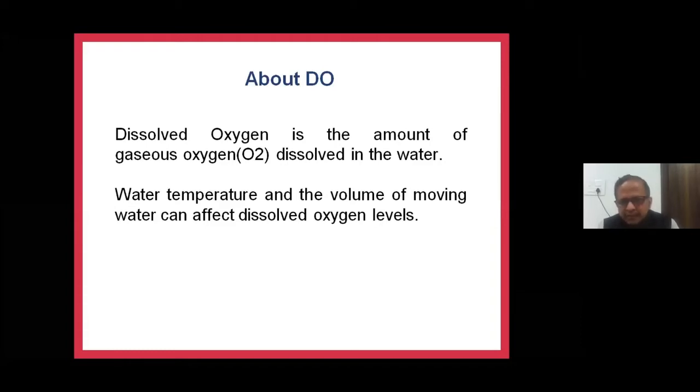And one more parameter is the DO, dissolved oxygen. One of the serious problems is whenever the septage or untreated wastewater is dumped into a water body, as I mentioned regarding BOD, it will take the dissolved oxygen in the water body to stabilize the septage or the sewage. In that process, the DO of the receiving environment, it may be a pond or a canal, will be reduced. So one more important parameter to understand the receiving environment before and after the treatment system is DO. And as the DO decreases beyond a level, even the aquatic life will be seriously impacted. Now and then we notice that fish are dying and floating.